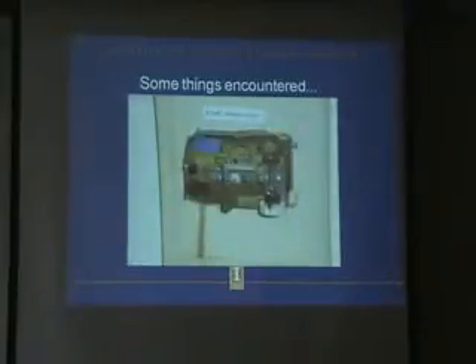This is a thermostat over in Turner. What's wrong with this picture is this: there's oil coming out of the pneumatic lines in this building. This really didn't cause a problem with this particular thermostat, but when you get into pneumatically controlled variable air volume boxes in the building, this will take out that controller and it won't work. So it's got to be replaced.